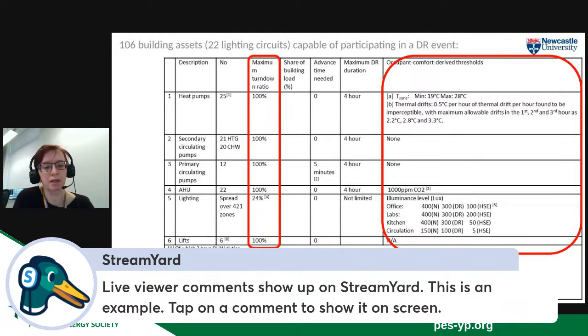And then the final load that we looked at was lighting. There's 22 lighting circuits that potentially could offer demand response, because we've always got the low-level emergency lighting circuits that could kick in if we wanted to turn down some of the lighting. But whilst the building's occupied, we don't want just the emergency lighting level. There are some minimums to ensure that we maintain from a Health and Safety Executive guideline point of view. So making sure that the lux level stays at no less than 300 for a demand response event.